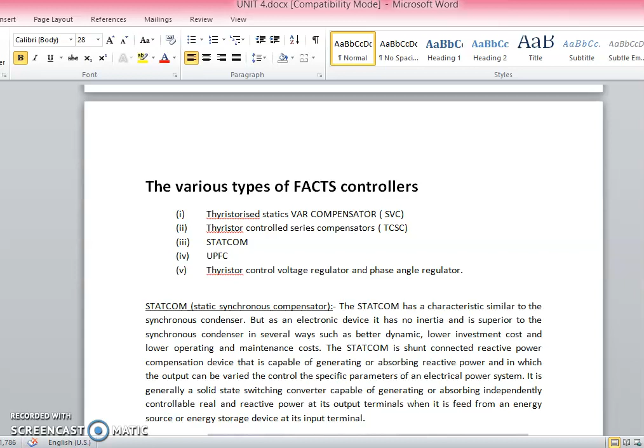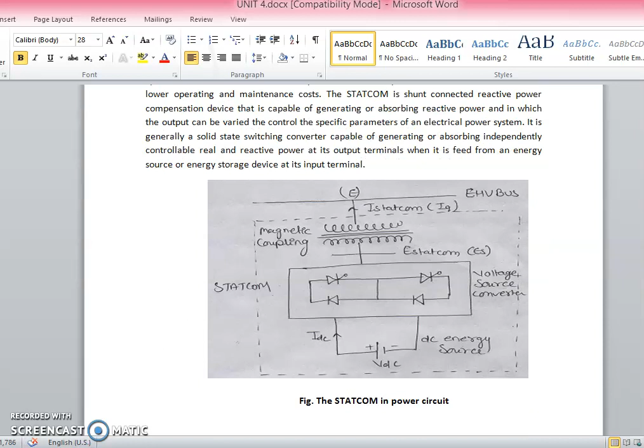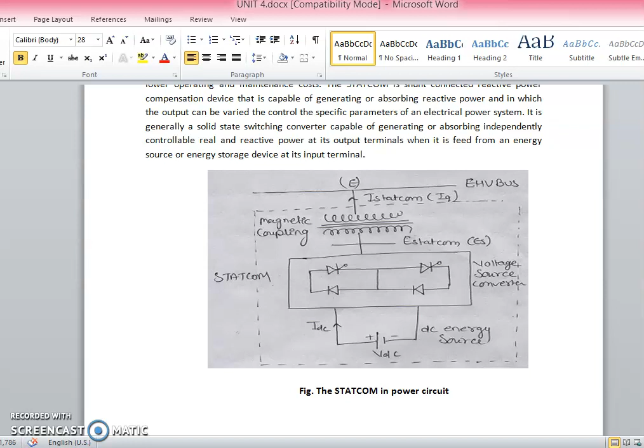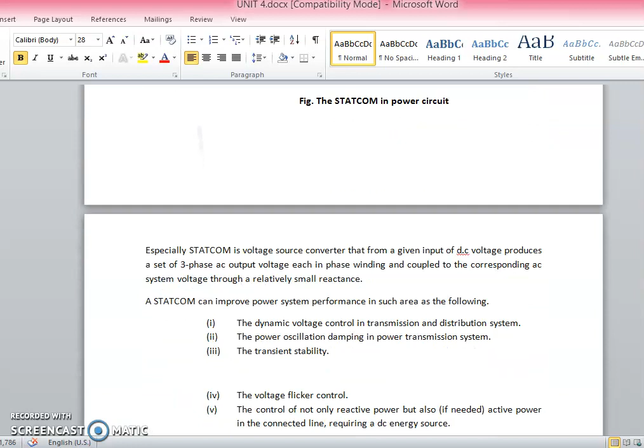It is generally a solid state switching converter capable of generating or absorbing independently controlled real and reactive power at its output terminal when it is fed from an energy source or energy storage device at its input terminal. This is the basic diagram of STATCOM in a power circuit: voltage source converter, DC energy source, and magnetic coupling with the associated EHV bus. Basically, STATCOM is a voltage source converter that from a given input of DC voltage produces a set of three-phase AC output voltages, each in phase with and coupled to the corresponding AC system voltage through a relatively small reactance.